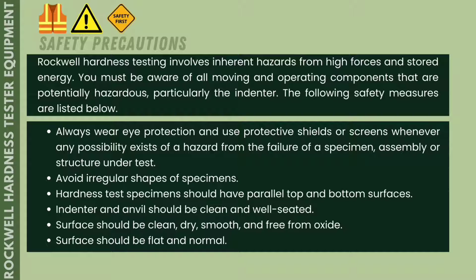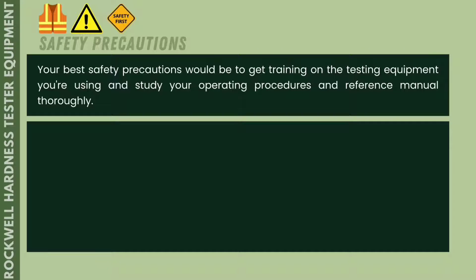Next, the indenter and anvil should be clean and well seated. Again, it is for accurate and safer testing. Next, the surface should be clean, dry, smooth, and free from oxide. So not just the indenter but also the surface. Next, the surface should be flat and normal. And the last one, your basic safety precaution would be to get training on the testing equipment you are using and study your operating procedures and reference manual thoroughly. Before you try testing the equipment, you must be knowledgeable enough, because it's safer when you know what you're doing. So those are the safety precautions to be considered when using a Rockwell hardness tester.